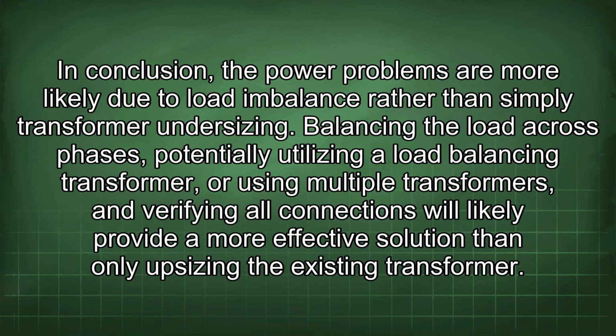In conclusion, the power problems are more likely due to load imbalance rather than simply transformer undersizing. Balancing the load across phases, potentially utilizing a load balancing transformer, or using multiple transformers, and verifying all connections will likely provide a more effective solution than only upsizing the existing transformer.